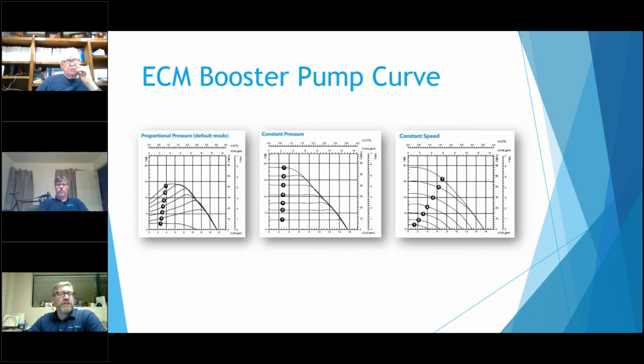And then these curves are kind of interesting. These are our ECM pump curves. You can see this one has a proportional control to it, so the pump curve looks a little wild where it's kind of coming up and going down. This one's a constant pressure, so it's going out to the edge of the pump curve. This one's a constant speed, so wherever it's on the dial setting, that's the pump curve it has.